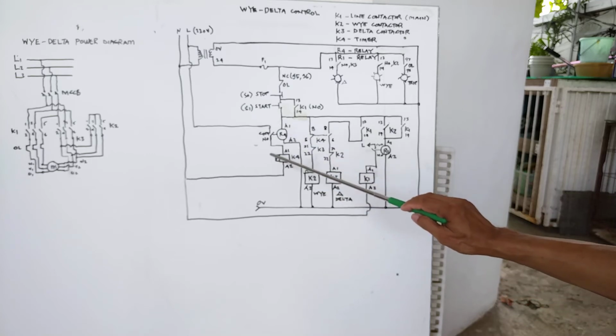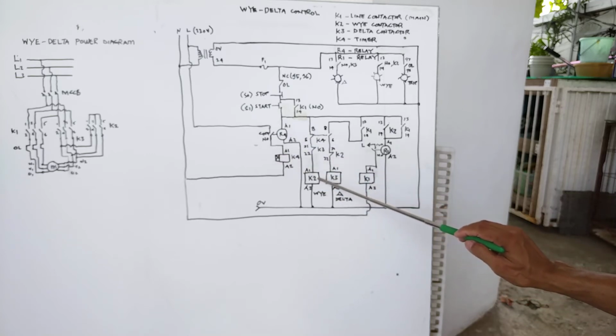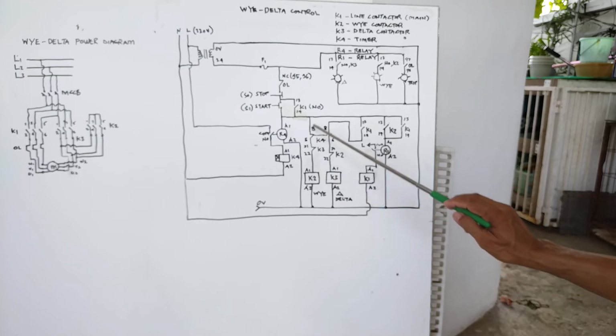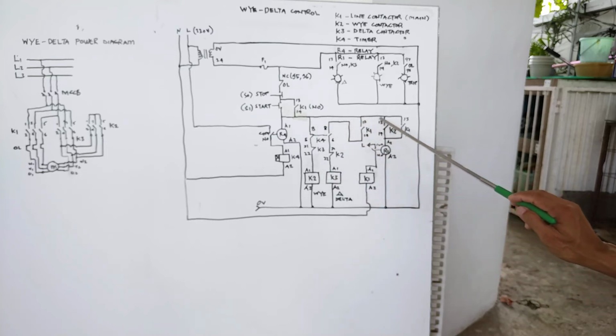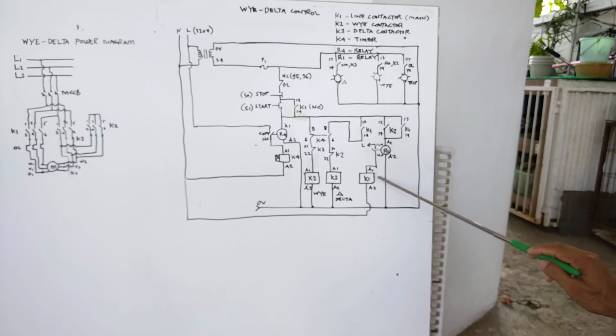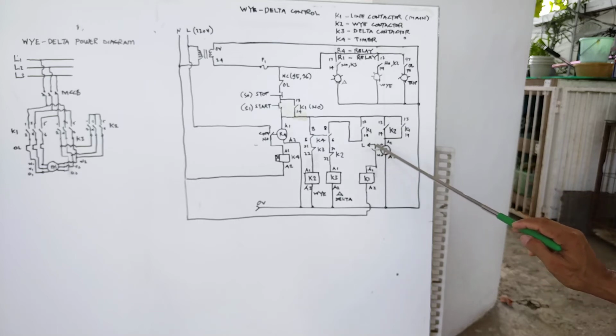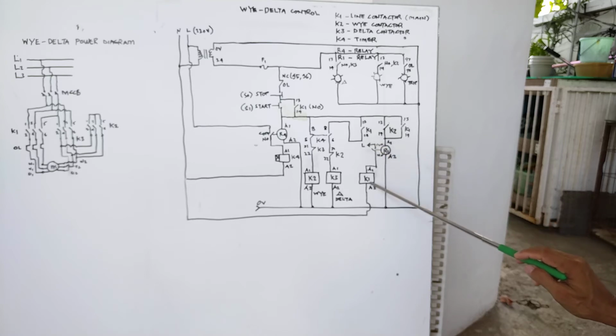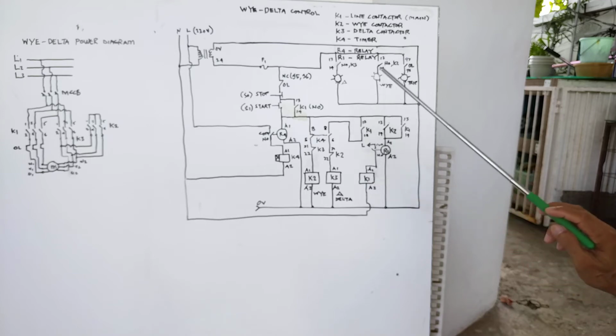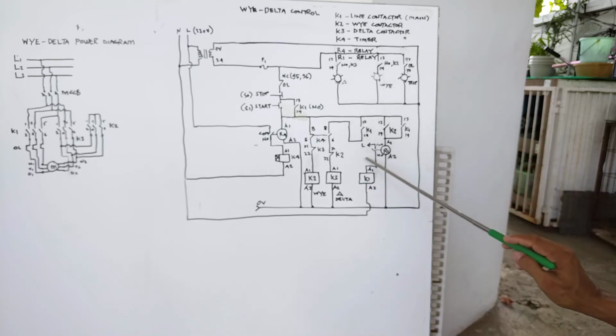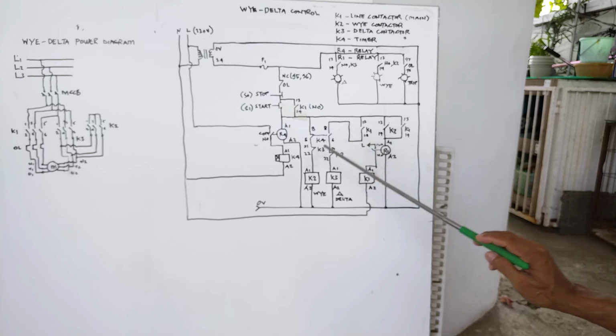So the timer is energized and the Y delta contactor, the Y contactor, is energized. At the same time, since this is energized, this one will close. So 24 volts will come here, then it will energize my line contactor because the common is connected to the 220. When this is energized, this one will close, then it will energize this one. So the line, timer, and Y are energized.